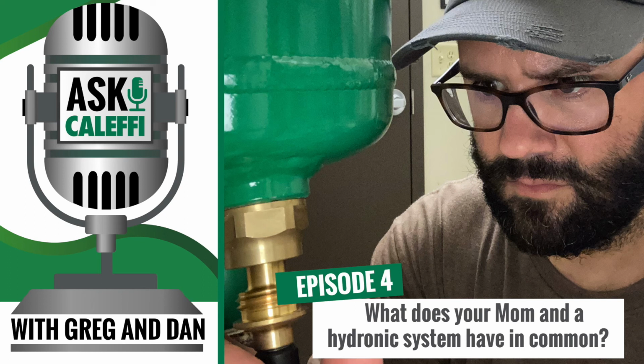Typically when a guy wants to know how to blow one of these off, we're going to tell him, hey man, you've got to turn off the pumps. Make sure the system's just sitting at rest. This makes sure all the magnetic material doesn't go back into the system when you pull the magnets, because a little suction from the pump can pull up the finer debris. Yeah, it can, especially once you pull that magnet out and release it. Pull the magnet and then you're able to open that drain valve. You'll do a downward flush, and generally you'll recommend continuing to let it flush for about 10 to 20 seconds after you see clear fluid coming out. Then you know you have that purged out. Then you can close up the valve and fire up the pumps again. Right. Put it back in service.